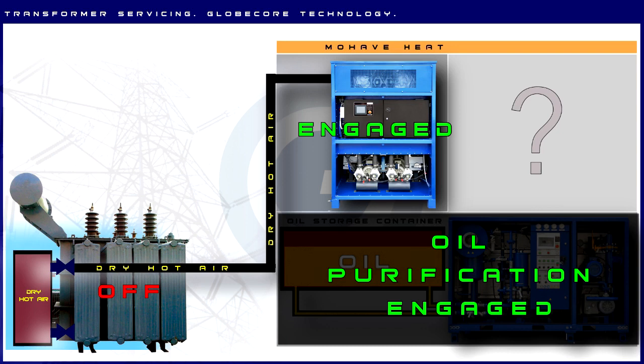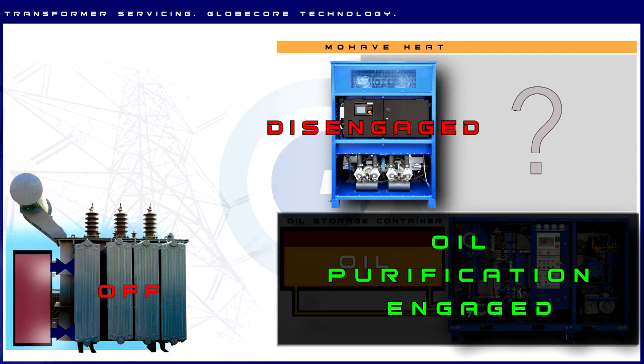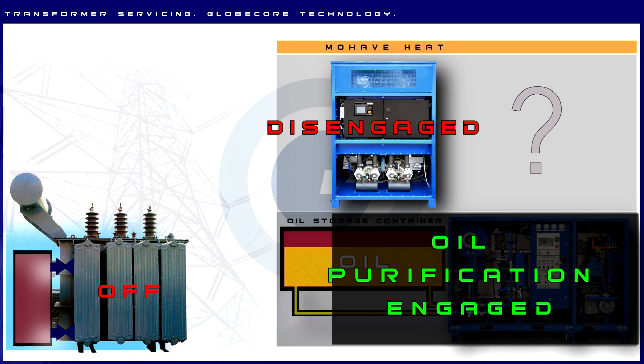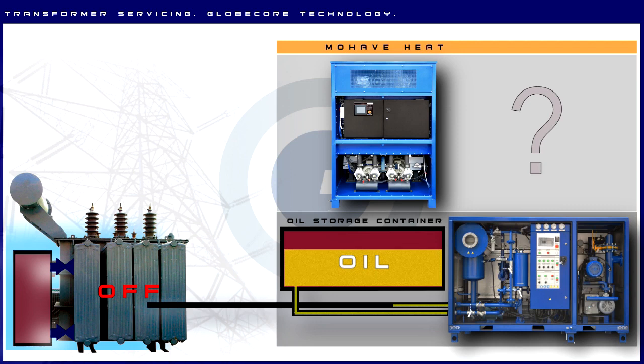When the necessary transformer repairs are complete, the Mohave Heat unit is disengaged and disconnected. The CMM-4D is stopped, and its outlet is switched from the oil container to the transformer. The purified and degassed oil is filled into the transformer.